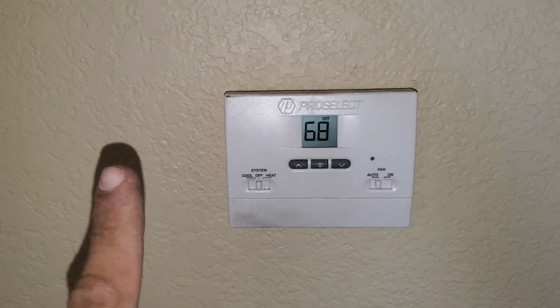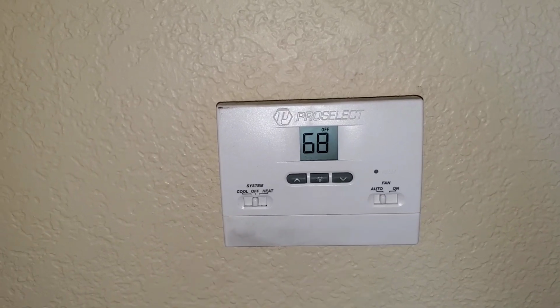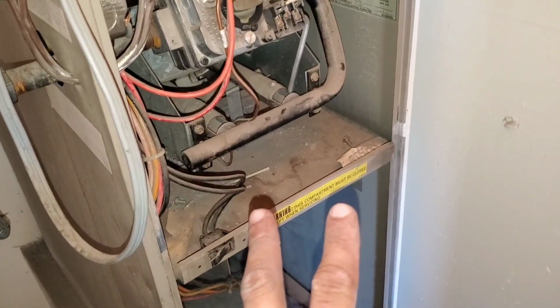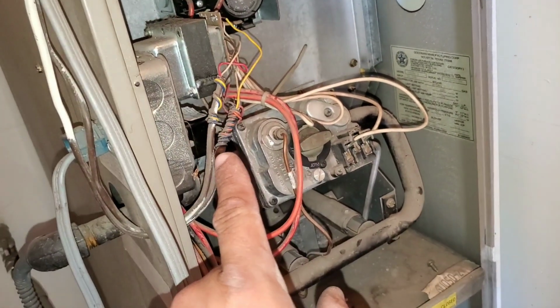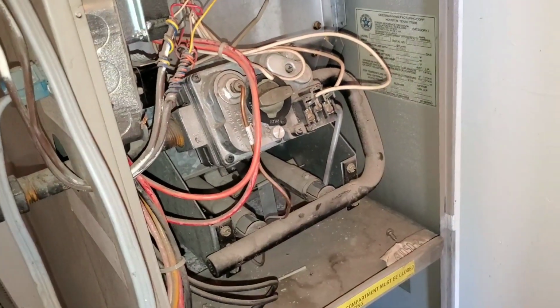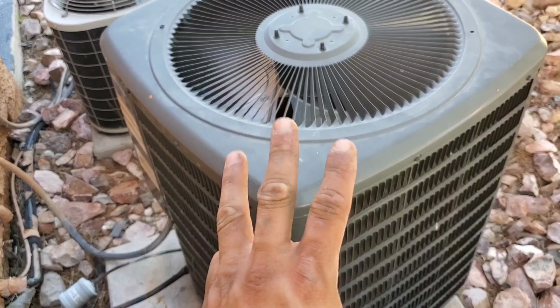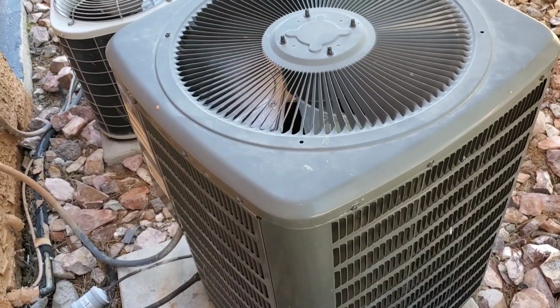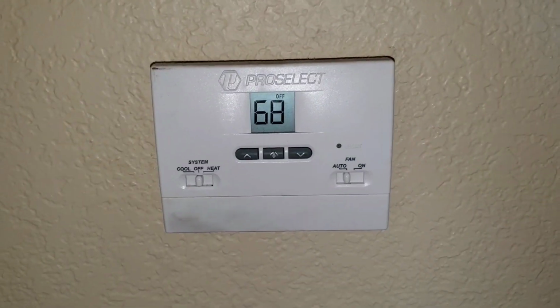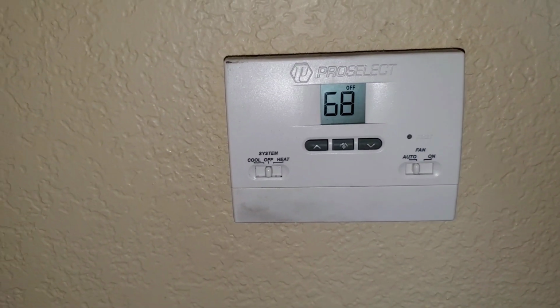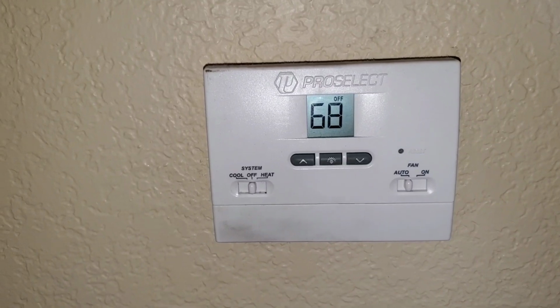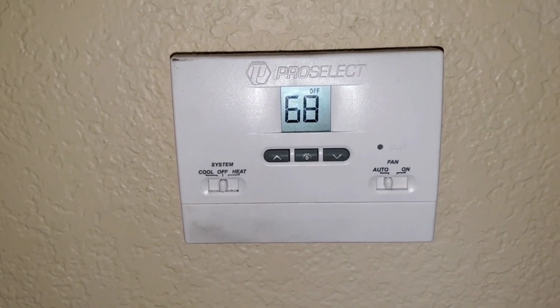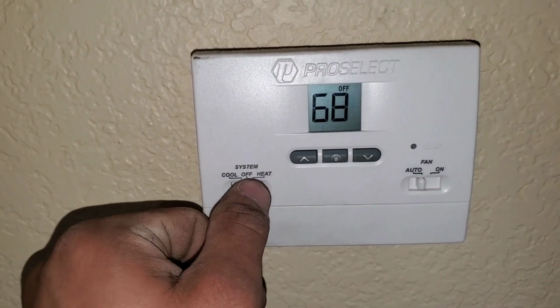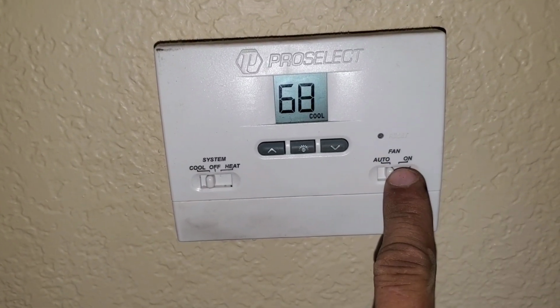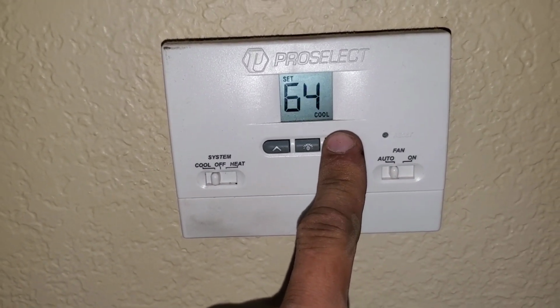Again, part one in troubleshooting, start at the thermostat. Part two of your troubleshooting, go to your return. Again, this is where the blower and your transformer and your relay are, and you may also have a board depending on your system. This will be part three of your troubleshooting when you're going through your system. Again, during this video, we are going to manipulate the system just to allow you to troubleshoot in your mind as we're going through this process. First thing we're going to do is set our thermostat to cool, make sure you're set to auto, and lower the ambient temperature.